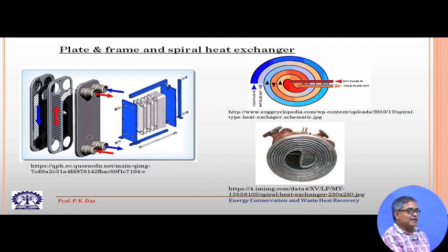So, you can see there could be a zigzag flow path, and again by providing this kind of flow path, we can increase the residence time of the fluid. Then many such plates will be placed one after another. Sealing will be done with the help of gaskets, and then they will be tightened in some sort of frame, which we will see in an animated film later on. And the advantage is that we get a very high rate of heat transfer because of this close contact.